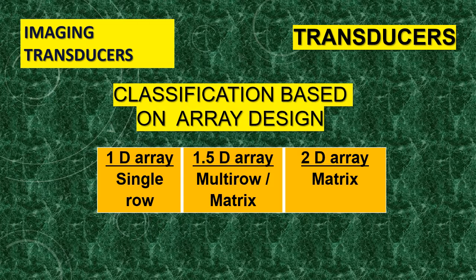We have three categories of transducer design: 1D array transducers, 1.5D array transducers, and 2D array transducers. In this lecture, we'll talk about the design of the active elements — how they are designed inside the transducer, whether in one row, two rows, three rows, or multiple rows.